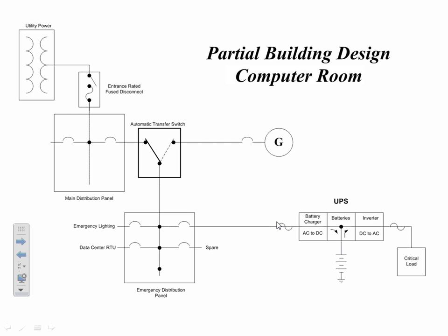Because we've designed a system like this, where the generator is now feeding and recharging batteries as well, and the critical load is still being fed, we call that a ride-through because of the UPS. The UPS gives us a ride-through between the utility failure and the supply by the generator set. It's carrying the load at that time, so it's riding it through. At the same time we're recharging the batteries in the UPS, we've also fired up some emergency lights, so the lights in our room are still working, and the air conditioning is still there. So it's a hot day outside, so the air conditioner is still running for the IT department. So it covers our critical load in that way.